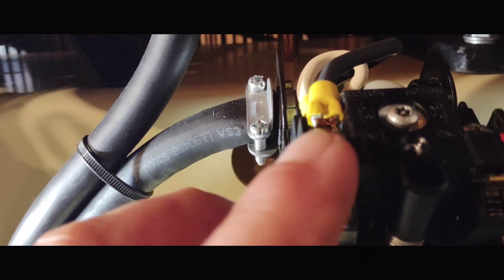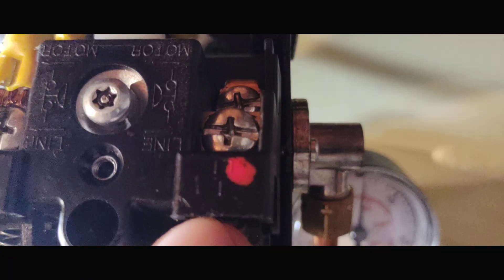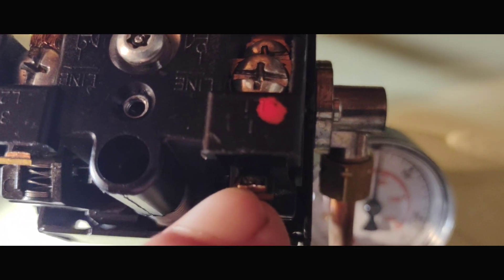These contactors are pretty burnt up. I did take and polish them up the best I could. That one looks okay, but this one here was kind of burnt up - you can see it's pretty nasty on the inside.